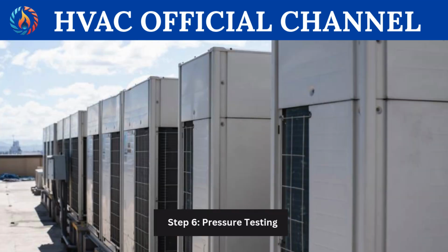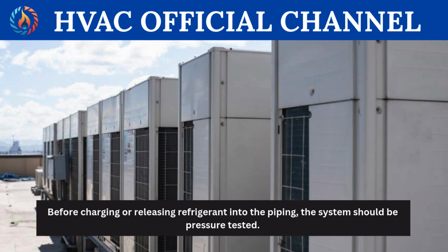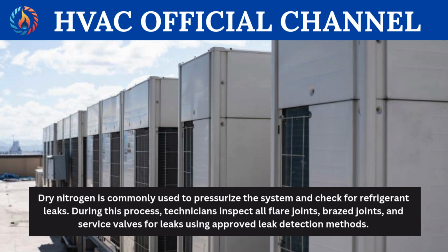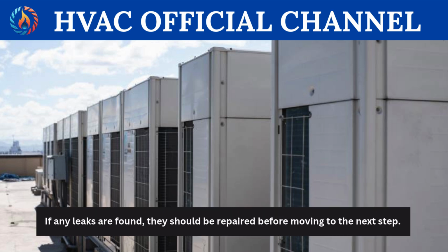Step 6. Pressure testing. Before charging or releasing refrigerant into the piping, the system should be pressure tested. Dry nitrogen is commonly used to pressurize the system and check for refrigerant leaks. During this process, technicians inspect all flare joints, braze joints, and service valves for leaks using approved leak detection methods. If any leaks are found, they should be repaired before moving to the next step.